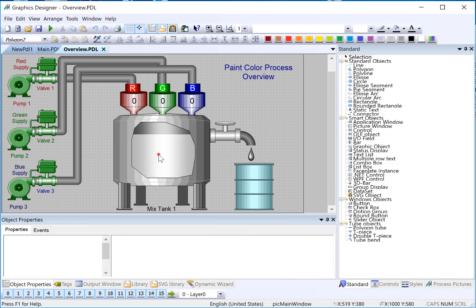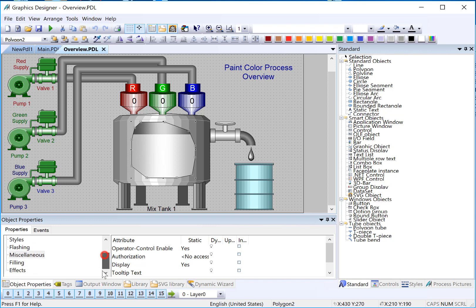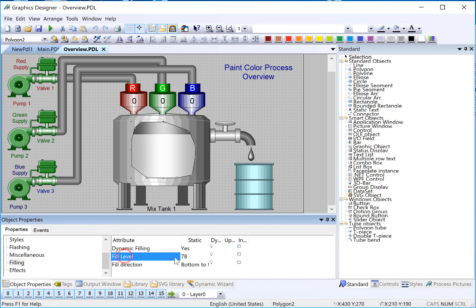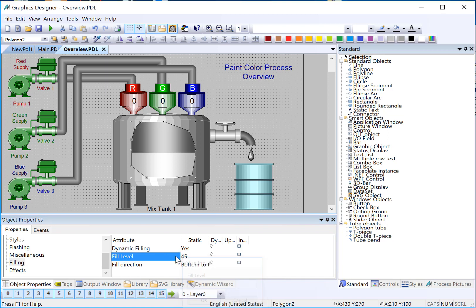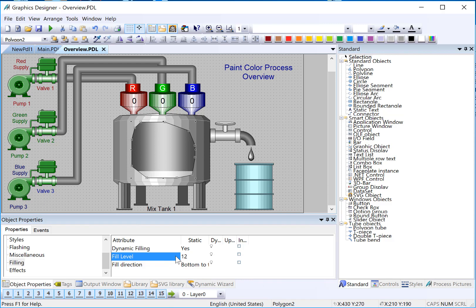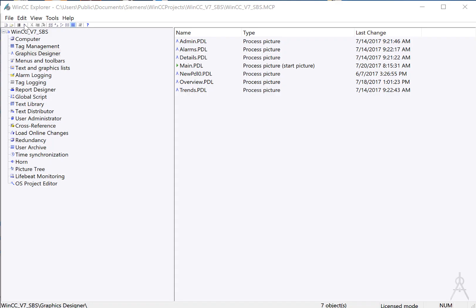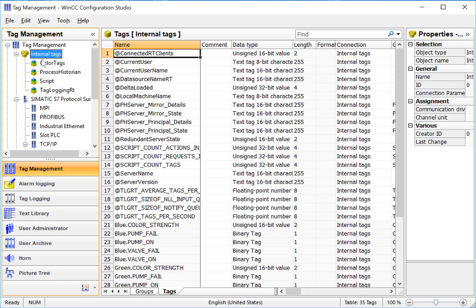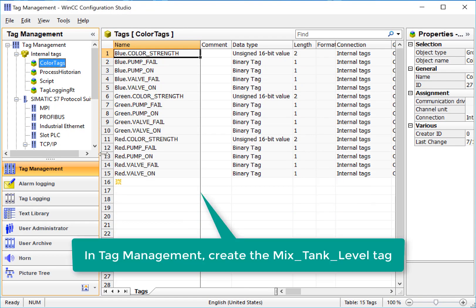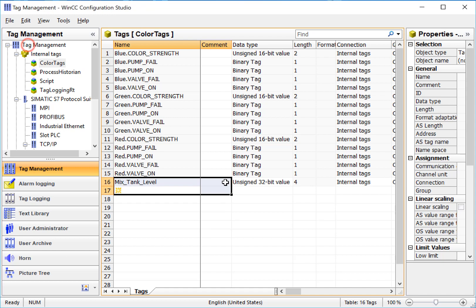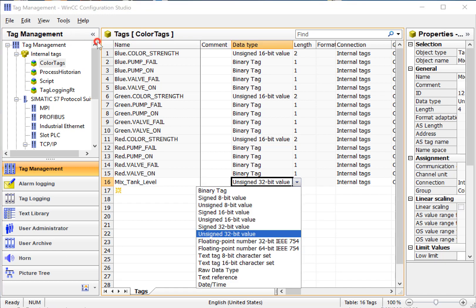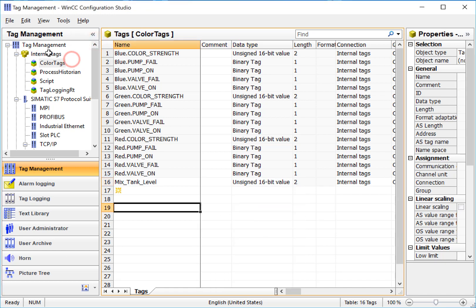First, we need to create an internal tag that is going to control the level of this tank, and we're going to hook it up directly to this fill level property, which determines what level the fill level object is. To do this, we'll go back to WinCC Explorer and open Tag Management. In Tag Management, under Internal Tags, we'll go to our Color Tags group and create a tag here. We'll call it Mix Tank Level, and we'll set it to be unsigned 16-bit value.